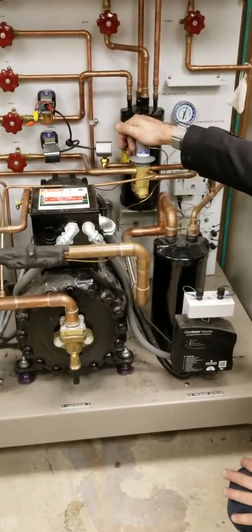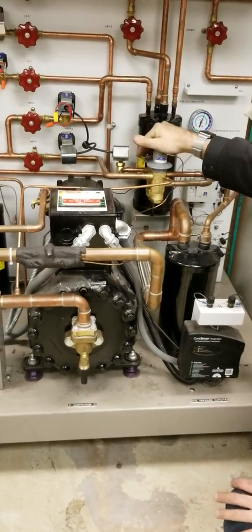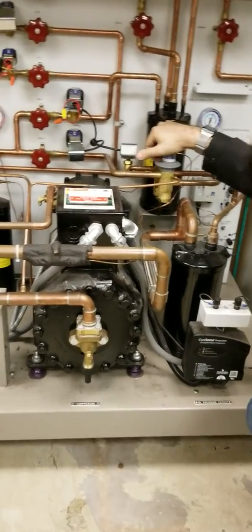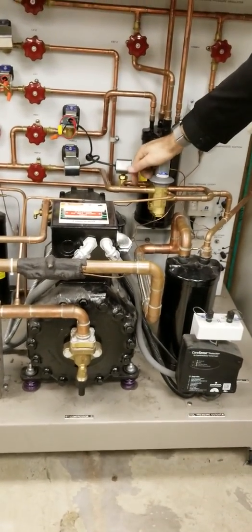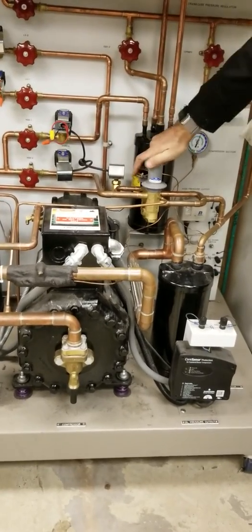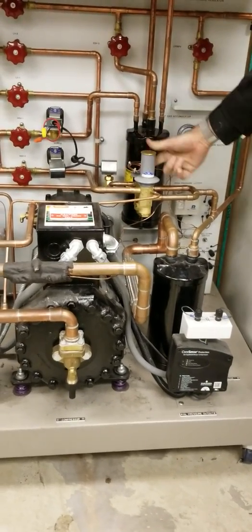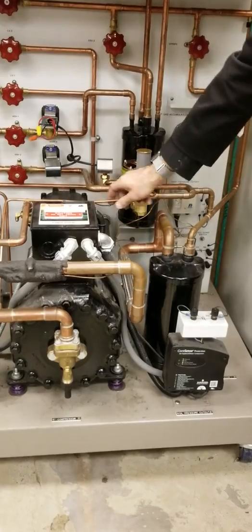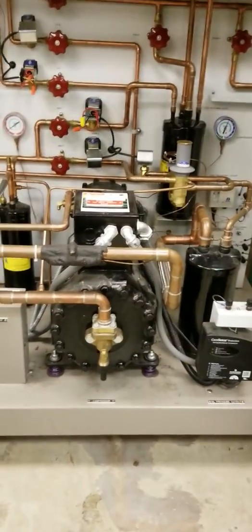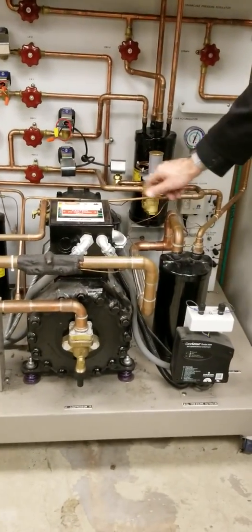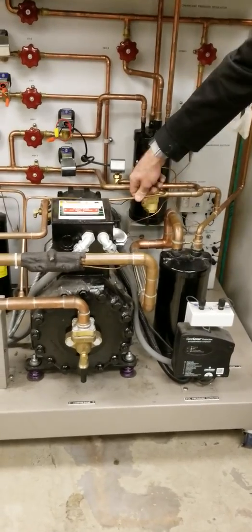You have these valves to spill in refrigerant whenever we get into another pressure drop. Pressure gets too low. This one is adjustable as well, where it's going to allow our refrigerant to be spilled directly into our suction line. Here's the external equalizer. So we go ahead and flip it on now.